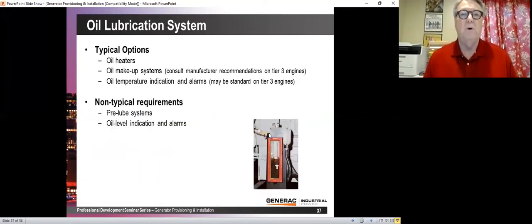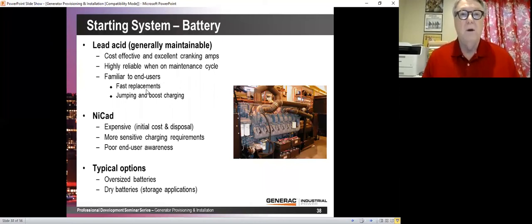Here's some typical options. Oil heaters. We generally don't recommend oil heaters. We don't want a heater in the oil, aging that oil. But when we get to very, very cold situations, maybe up on a mountaintop where it gets really cold, we may look at putting in an oil heater. We never put in heaters in the tank for the diesel fuel. That would be virtually impossible to create a heater that large. And again, that would cause problems with your diesel fuel. So we need to make sure that it just has anti-gelling compounds and is appropriate for the level of the temperature, I should say. Make sure you don't get gelling of the diesel fuel, which of course is a big problem.